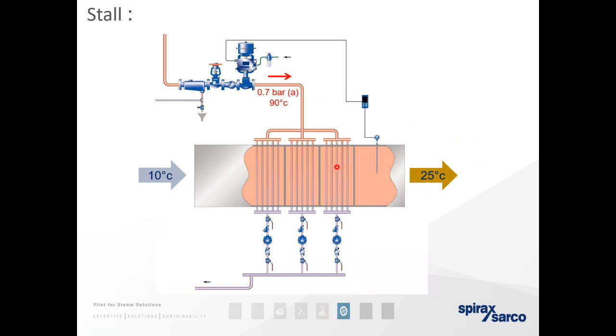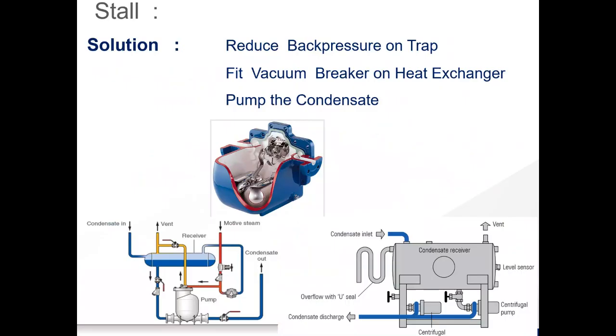So here, when demand for heating lowers, you'll see the control valve starts to close. So you get a pressure drop here. This then can be lower than the pressure that's in your traps, which increases the buildup of condensate in the coil, which then decreases the efficiency of those coils. And that's what we call stall. So how we could remove that.